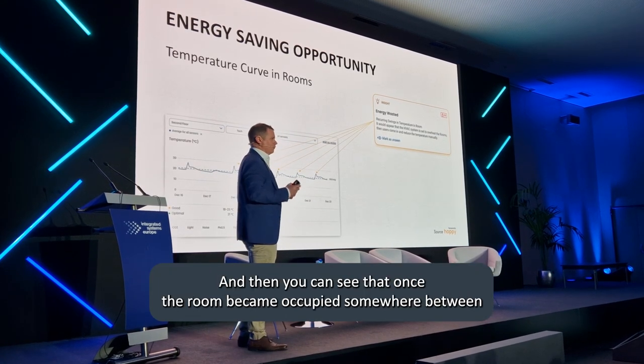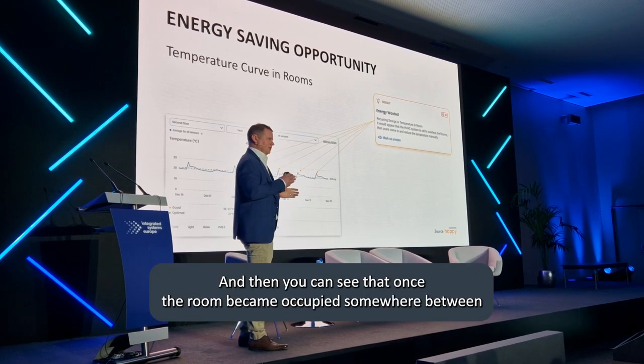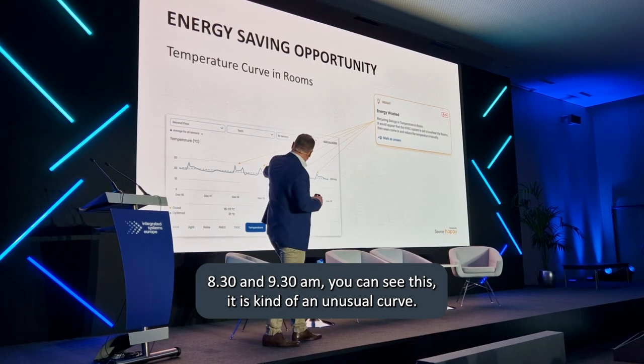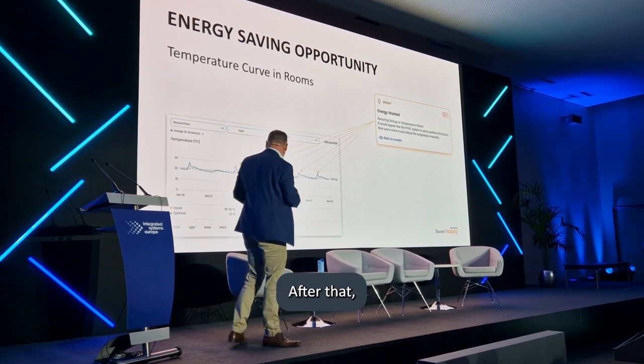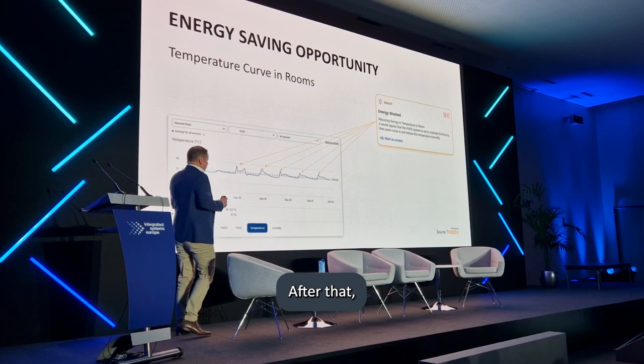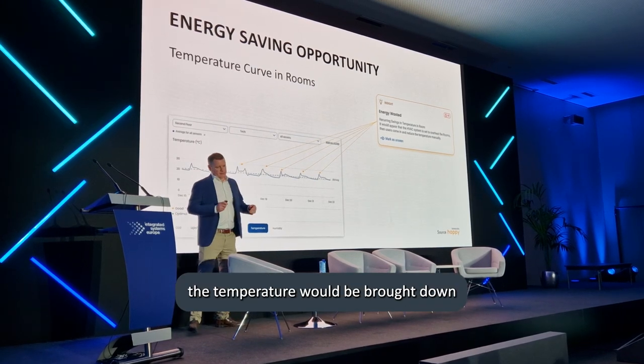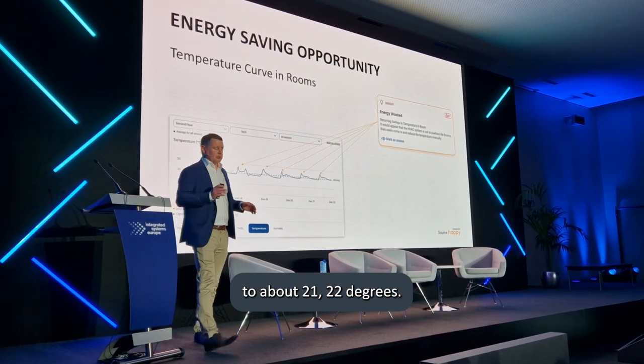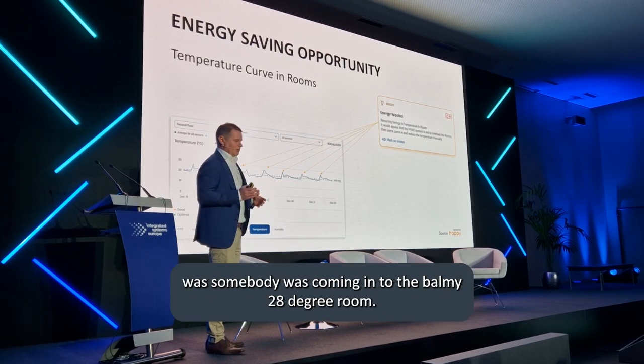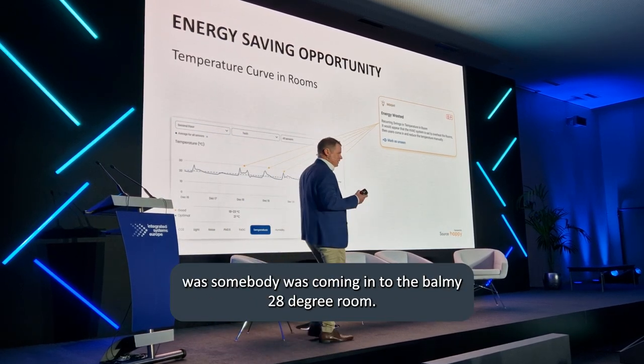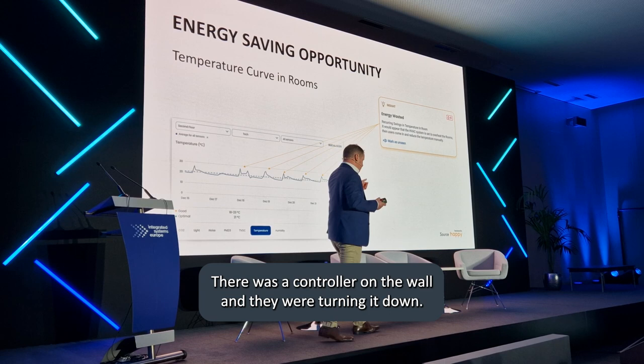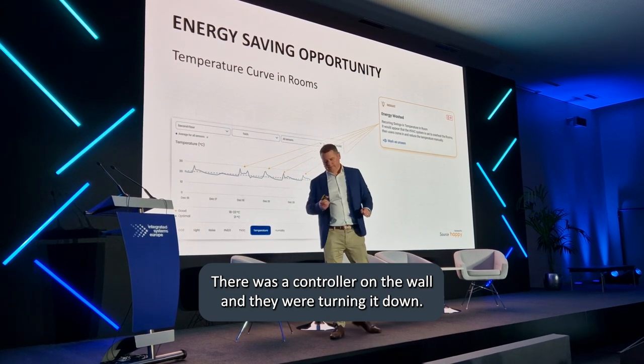Once the room became occupied, somewhere between 8:30 and 9:30 a.m., you can see this unusual curve after that - the temperature would be brought down to about 21, 22 degrees. So what was actually happening was somebody was coming into the balmy 28 degree room, there was a controller on the wall, and they were turning it down.